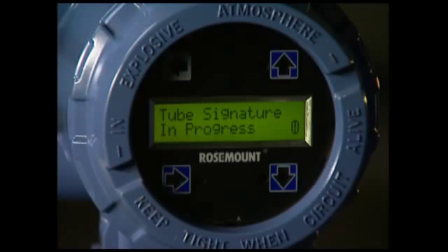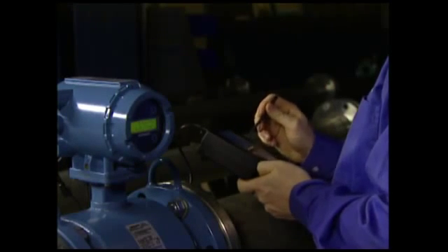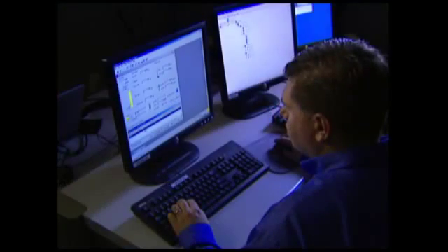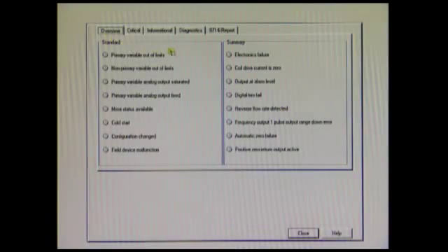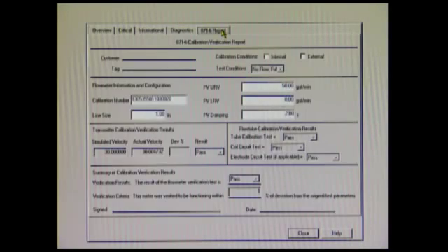The 8714i diagnostic can be initiated via the local operator interface, a 375 field communicator, or AMS Device Manager software. With AMS Device Manager, verification results are automatically entered into a report that can be printed out for your records.